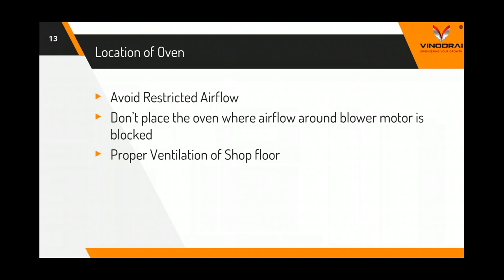We also need to make sure that the burnt gas has a place to go out of the shop floor, so that the oxygen ratio of the air on the shop floor doesn't lower, which would again lead to lower oxygen air being sucked by the burner, which would not lead to complete combustion and thus fuel inefficiency.